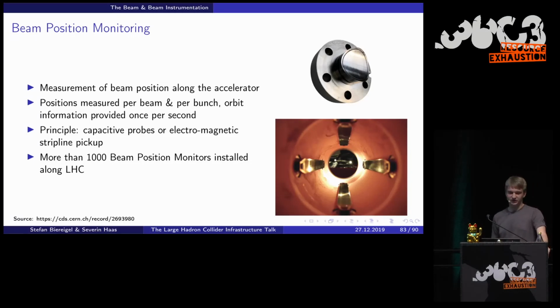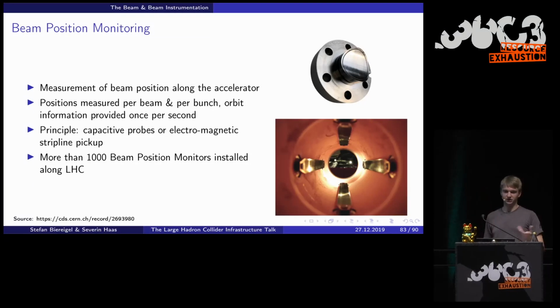Then number 3 that we have is the beam position monitor, because along the LHC, you also always want to know where the beam is at any given time. So you want to measure the position of the beam inside the beam pipe in order to optimally adjust it to the position you want to have it. For that, we use these beam position monitors, of which we have more than 1,000 installed along the LHC. They are typically capacitive probes or electromagnetic strip lines, as you can see on top and bottom respectively. They are distributed along the LHC and provide the position of the particle beam along the accelerator, which can then be used to tune, for example, the magnets.